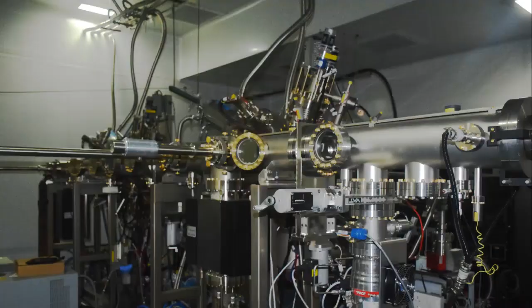When samples have to be loaded into the chamber, we take them out from the boxes, place them within the chamber, and then take them out from the chamber again. We never allow the samples to be exposed to the open atmosphere or high temperature. That's why these electron microscopes are housed in this clean room, and class 10,000 is sufficient for that.